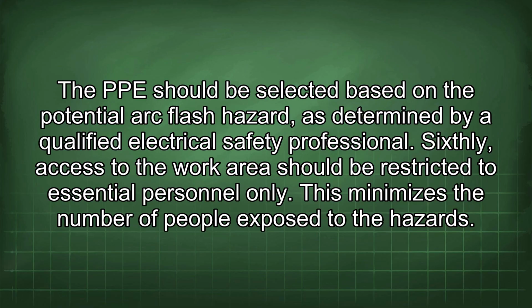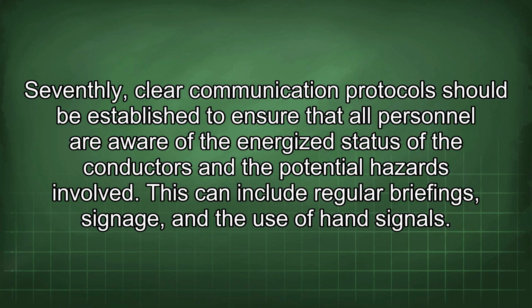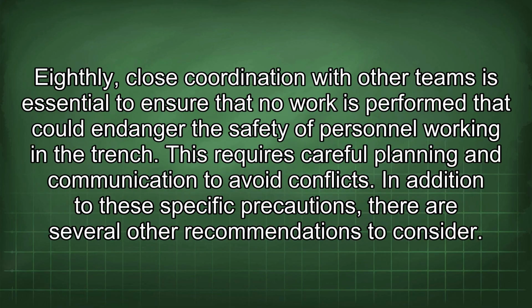Sixthly, access to the work area should be restricted to essential personnel only. This minimizes the number of people exposed to the hazards. Seventhly, clear communication protocols should be established to ensure that all personnel are aware of the energized status of the conductors and the potential hazards involved. This can include regular briefings, signage, and the use of hand signals. Eighthly, close coordination with other teams is essential to ensure that no work is performed that could endanger the safety of personnel working in the trench. This requires careful planning and communication to avoid conflicts.